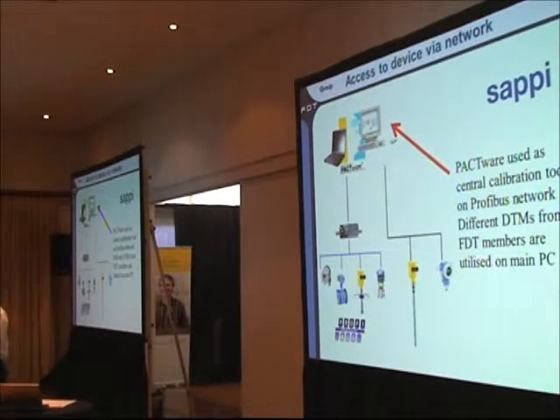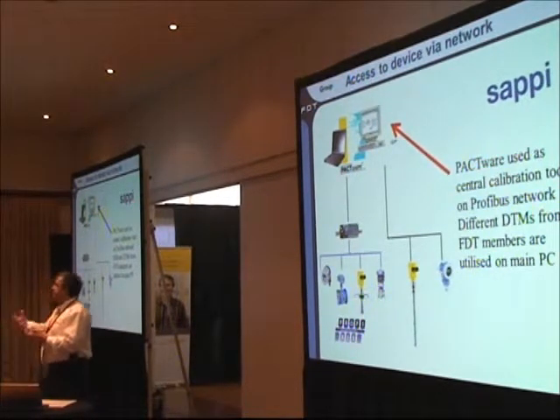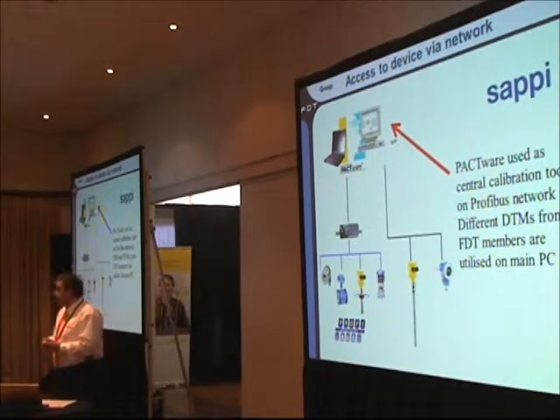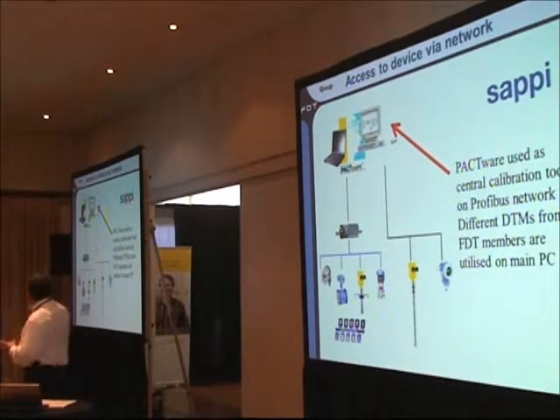With Profibus it is sometimes more comfortable than only HART, because Profibus itself is a little bit faster, with 31.25 kilobits per second. HART is relatively slow, with 1.2 kilobit per second, but mostly it's enough.